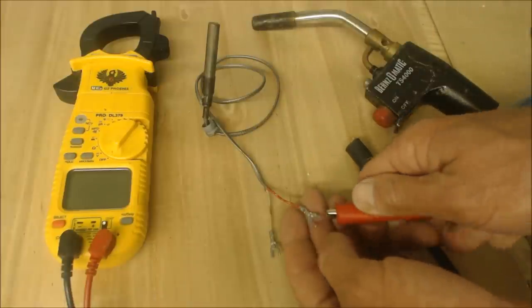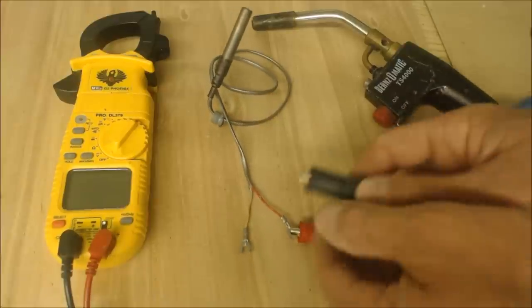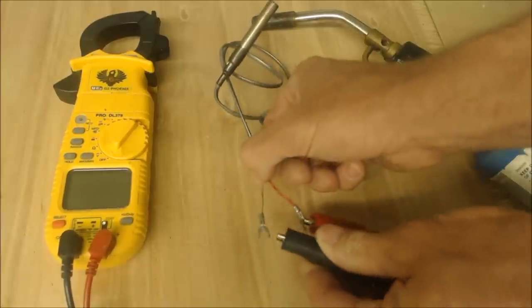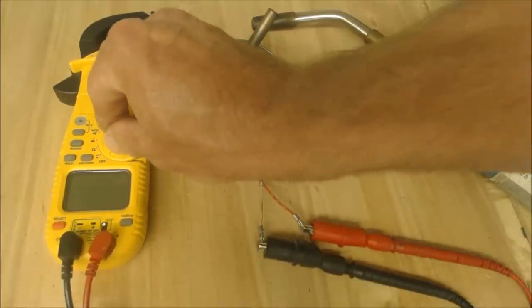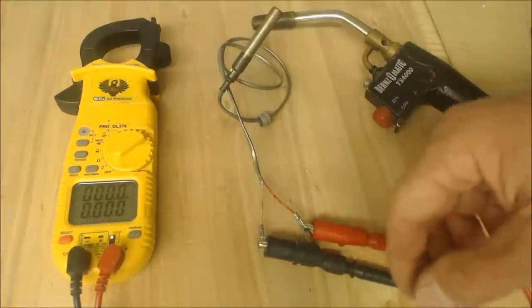So we're going to go ahead and connect onto our terminals, and then we're going to go ahead and heat this up. We're going to be looking for 750 millivolts DC.